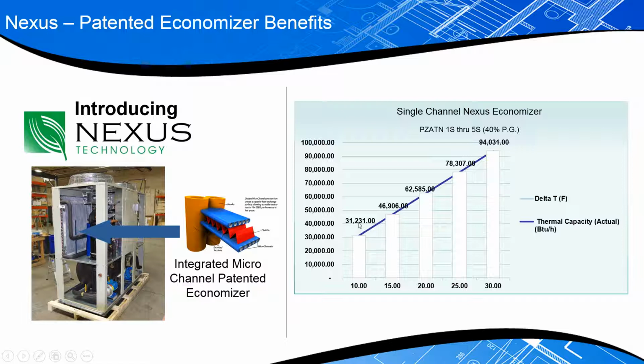It actually can be quite significant, and what this is here is the delta T between the tank temperature, which is down here, and the ambient temperature. So if we have a call for cooling, for example, and we have a 20-degree temperature differential between the outdoor air and the tank, the economizer can actually put out a significant amount of cooling, right? So this is really great if you get into a situation where you have a higher set point. You know, let's say it's an MRI or a CT, and those things run at 55, sometimes 60 degrees fluid temperature, and you're in a very cold climate like Winnipeg or someplace in Detroit, Michigan. A lot of times the mechanical cooling can go to sleep around November and not actually come back online until April.